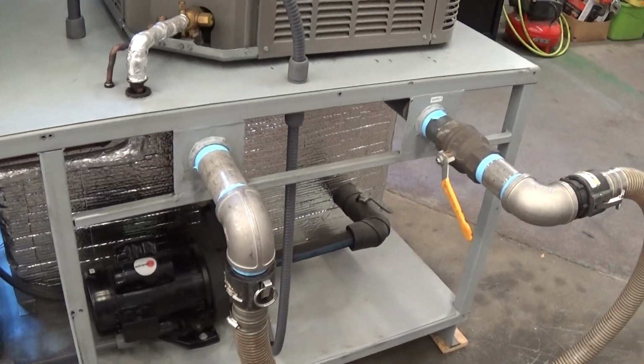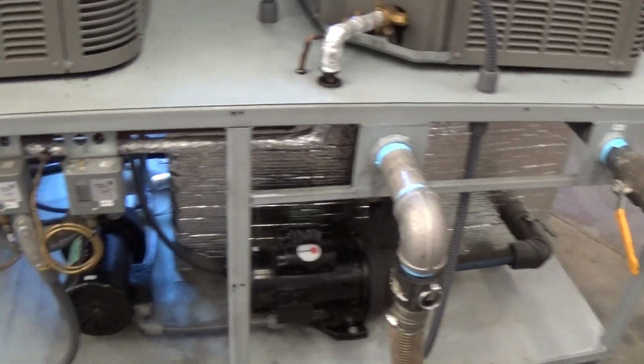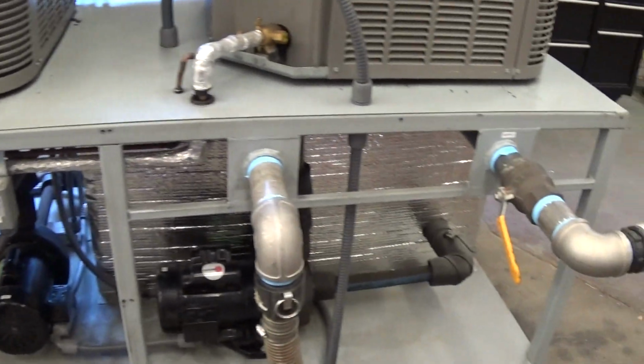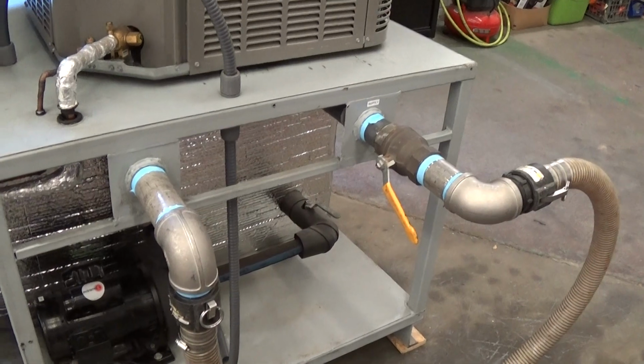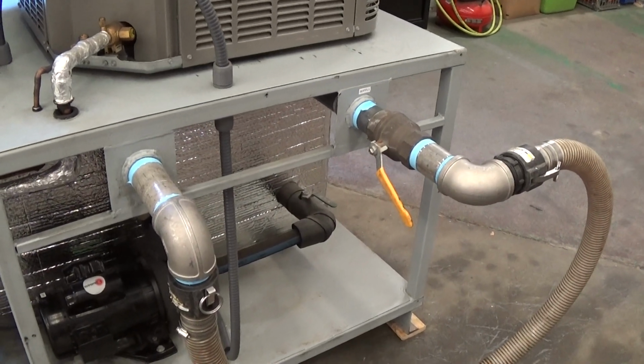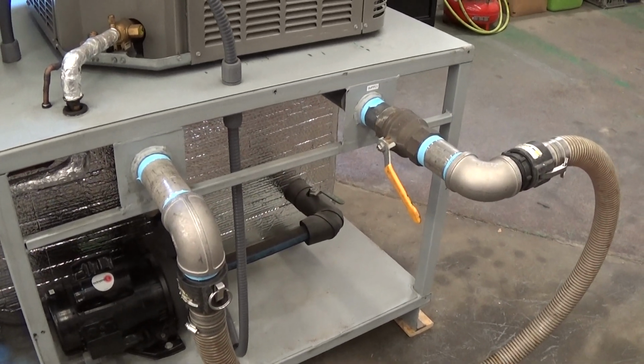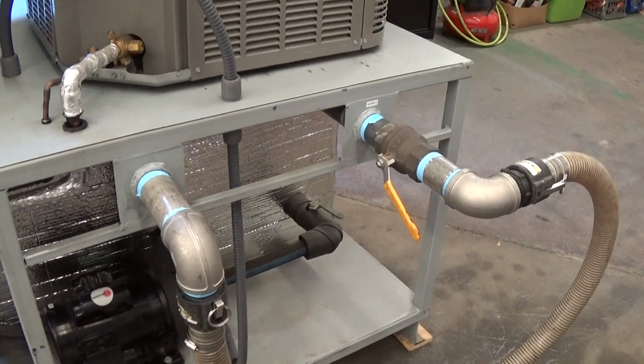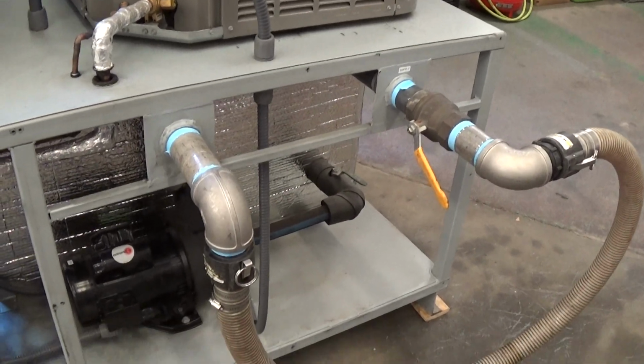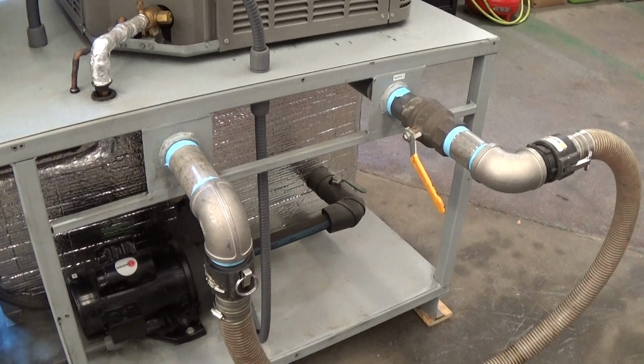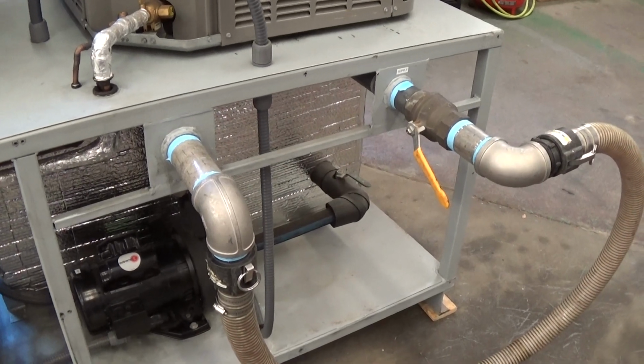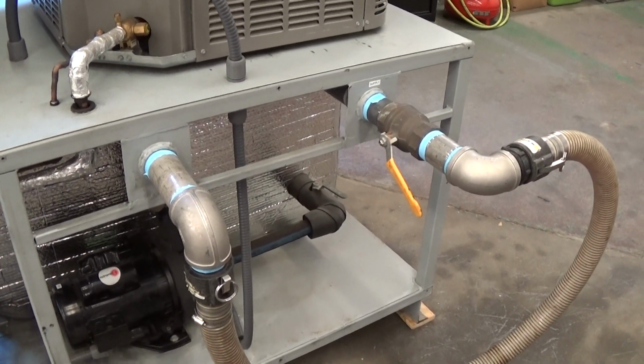Because we have the 2-pump system, it solves a lot of problems as far as dialing in the chiller when it's out in the field. Also, as far as a bypass, we really don't need to worry about a spring-loaded pressure relief bypass in the glycol loop, which is important on a single pump system to satisfy the flow coming back to the evaporators.